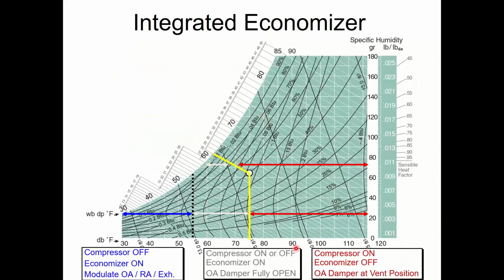This is the way I like to graph that out. If it's below 55 degrees outside, my old traditional black line, most systems are designed to provide 55 degree supply air, so it's below 55 outside, I probably don't need a compressor. My economizer should get it all done all by his lonesome. If it's above that 75 or above my 28 enthalpy, well then I'm not even going to try the economizer. I'm just going to use the compressor only, so I'm over here. And then anything in the middle is going to be my integrated economizer time, meaning I'm going to possibly run the economizer at the same time as the compression.